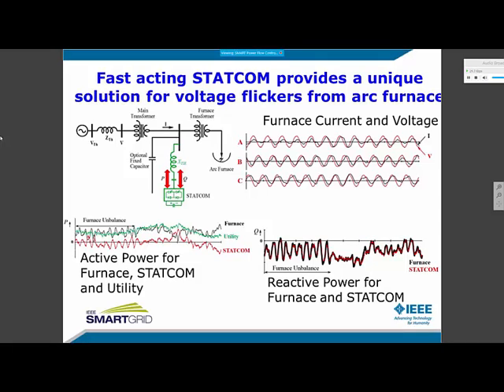When an arc furnace needs compensation, we tried out using an inverter-based STATCOM, because the furnace has this kind of voltage and current requirement from the utility. Since the current varies drastically or randomly, the voltage drop across the source impedance, the Thevenin impedance, also changes abruptly. So the voltage at the entrance to the plant has what we call flicker, that is a random change of voltage. Now, the STATCOM provides the reactive power needed by the furnace, as you see in this figure.